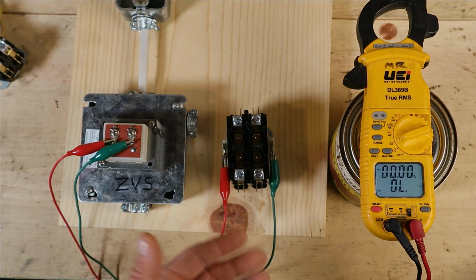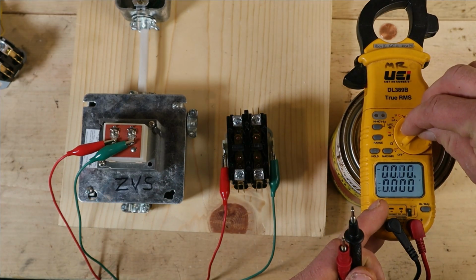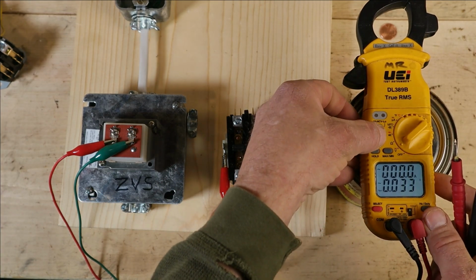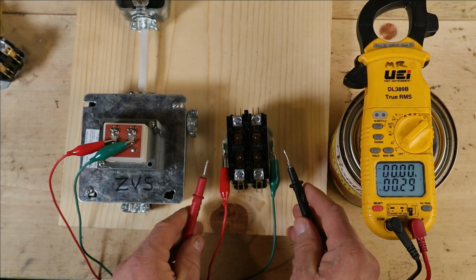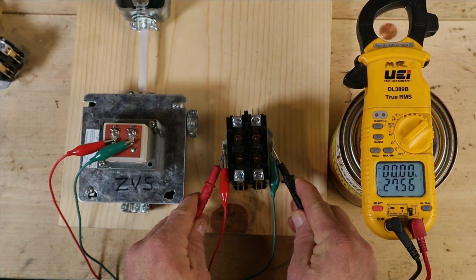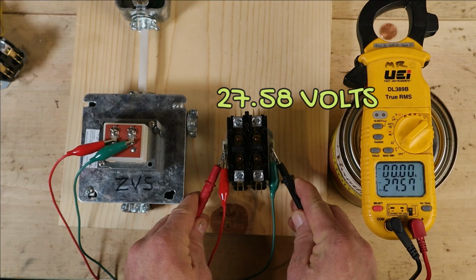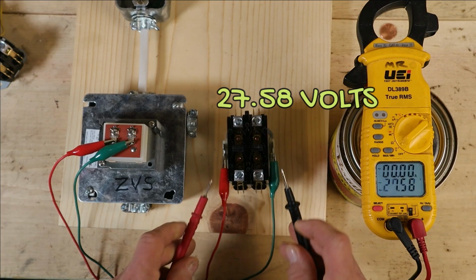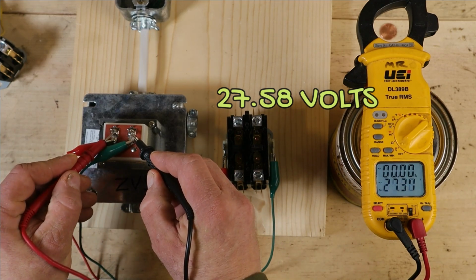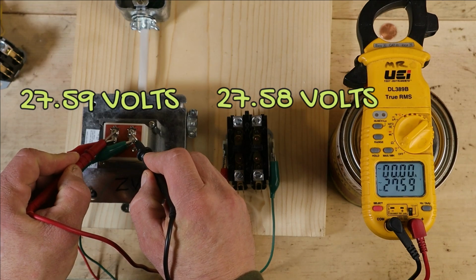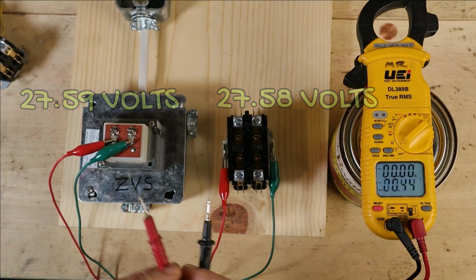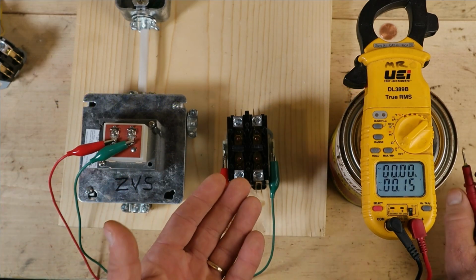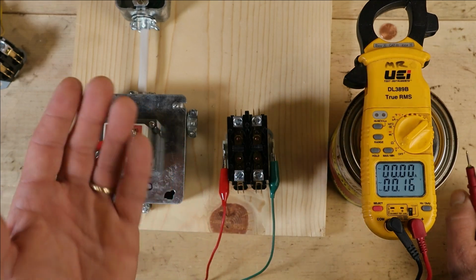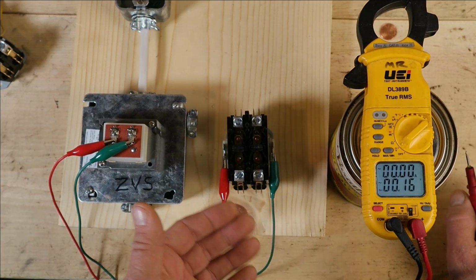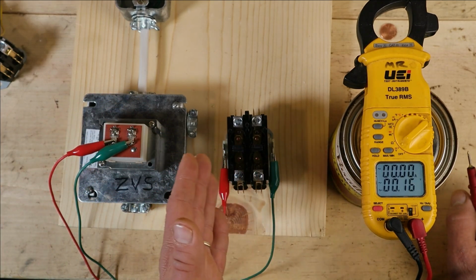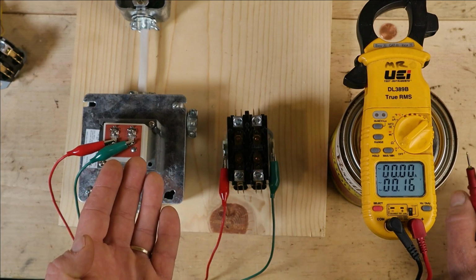You can see our contactor pulled in. We're going to go back to voltage, make sure we're in the proper range, and then take a voltage reading across the coil here. And you can see we're reading 27.5 volts. Now if we go off the transformer, we are also reading 27.5 volts. So what we see here is no matter what the resistance is, whether it's 1,000 ohms or 12 ohms, we're still getting the full voltage across these components that the transformer is putting out.